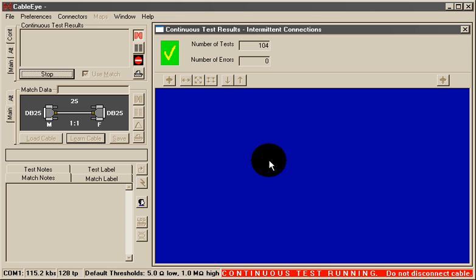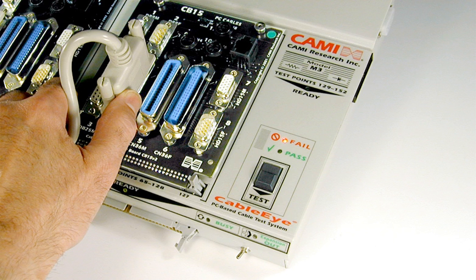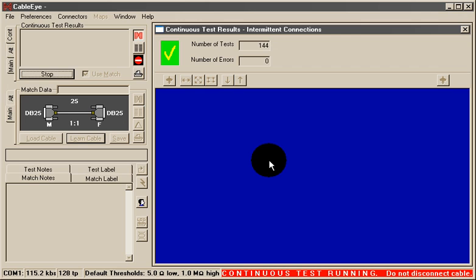Now flex the cable during this test to try to induce a problem. If an intermittent connection disrupts continuity, a tone sounds and the intermittent wire appears highlighted in the display.